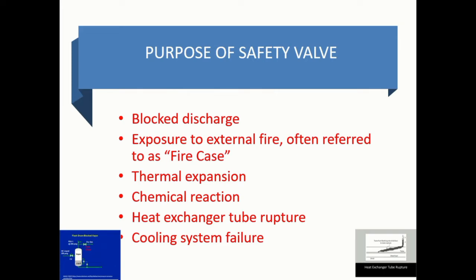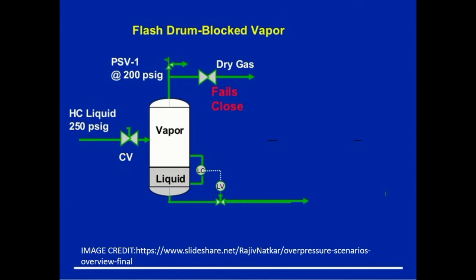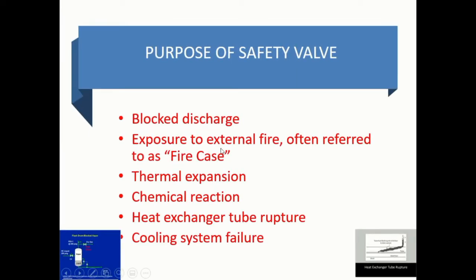Now we will see the purpose of using the safety valve. Suppose there is a blockage of the device — for example, in a flash drum where blockage vapor is present. Because of the blockage, vapor can pressurize the liquid, and in such cases we need to exhaust it into the atmosphere or into another vessel. Whenever the pressure reaches 200 psig, it will exhaust to atmosphere or another vessel. Next is exposure to fire — whenever there is a fire, temperature increases, and since temperature is directly proportional to pressure, overpressure occurs and the safety valve reacts.